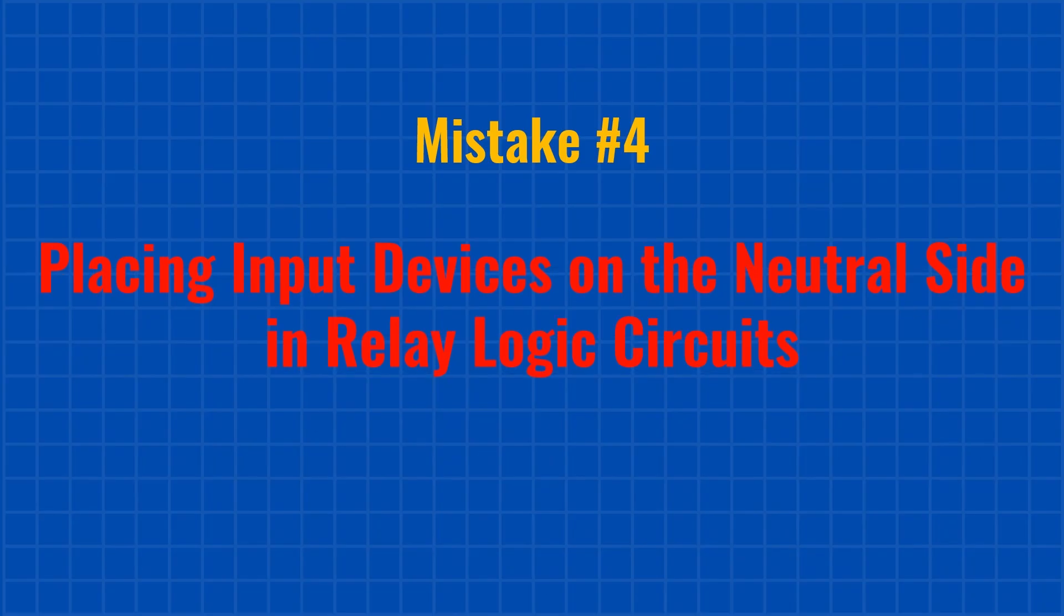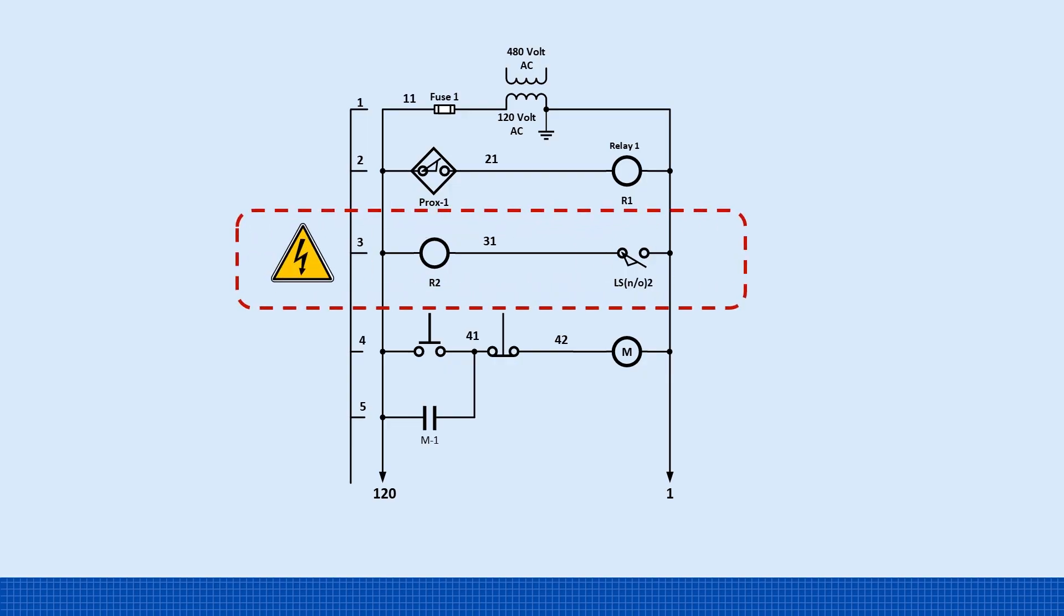Mistake number four. Placing the input devices on the neutral side in relay logic circuits. This mistake often happens when someone modifies a control circuit. In this example, line three shows relay two connected to the hot side, while the input limit switch is placed on the neutral side. Even though the circuit works, this is not good practice. According to the NEC, National Electrical Code, and IEC standards, control devices like push buttons and limit switches must interrupt the hot, line side, not the neutral.